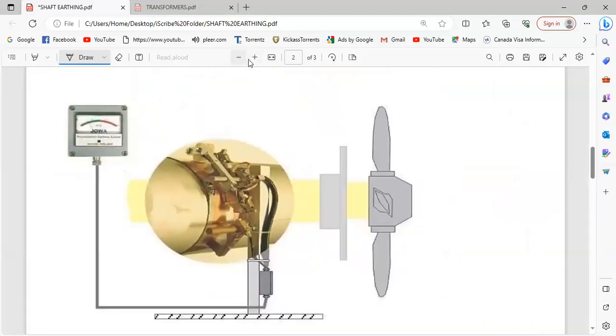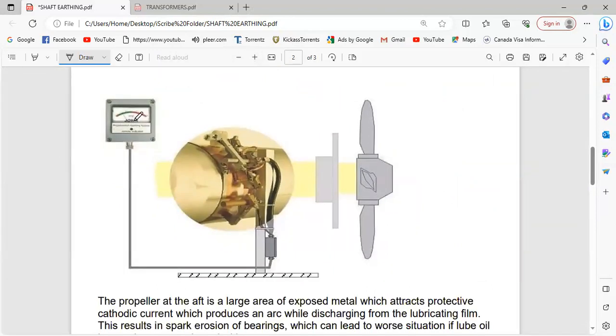Now you can see that there is a meter over here. Every morning we take the readings. Okay, and the reading on the meter should be in the green portion. Generally, I'm not saying every time, it is between 5 and 30 milliamps. Each manufacturer will have different specifications. Some I've seen up to 80 milliamps. So if you go beyond that 80 milliamps, and in this case, beyond 50 milliamps, that means your particular brushes are dirty. So you'll have to clean them.